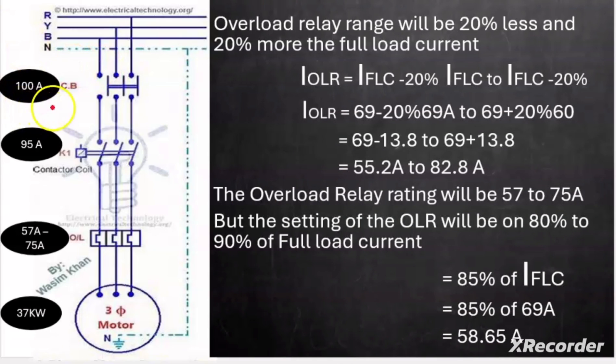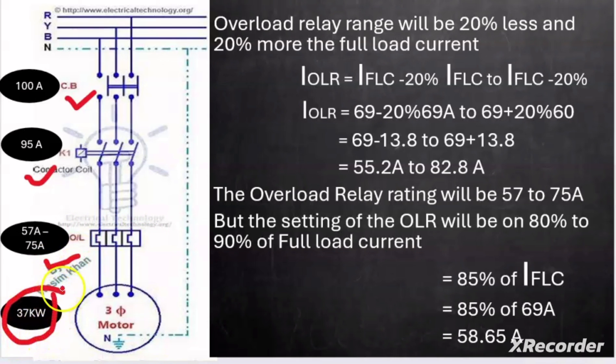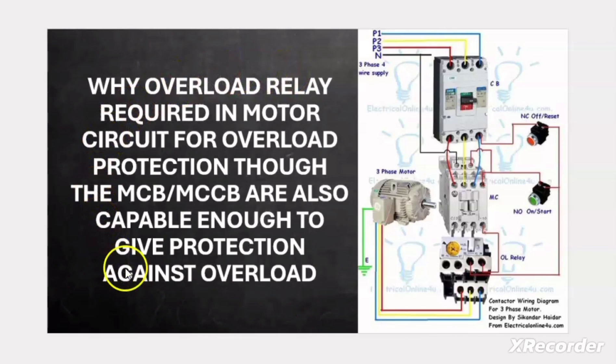To summarize: for a 37 kW motor, the circuit breaker rating is 100A (C type MCCB), the contactor rating is 95A (AC3 type), and the overload relay range is 57A to 75A set at 58.65A. I hope you clearly understood this topic.